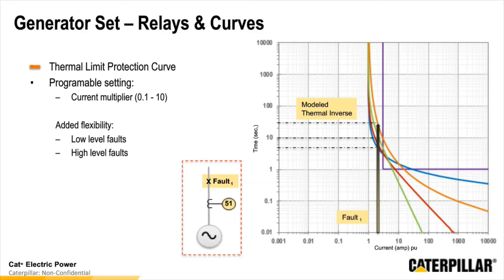There is one additional curve that's available in most generator sets, or in Caterpillar's generator sets. There is the thermal limit protection curve. The thermal limit protection curve does not have a time multiplier. It only has a current multiplier. And this curve is intended to follow what would be the rating of the insulation class material that you have. So in this case, we would see that we can now get more time in the long-term settings over to the left of the curve, and we can use the current multiplier to now move that across the x-axis. The reason why you would have the current multiplier would be because of the ability to have an oversize, or that you would want to reduce that a little bit so that you're not taking into account more current than is necessary.